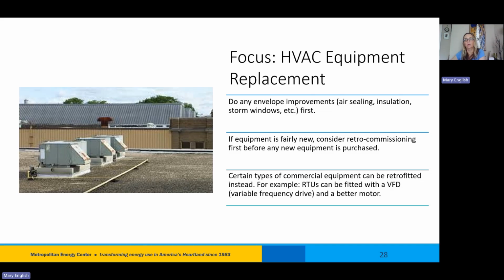Certain types of commercial equipment can be retrofitted, much like you retrofit your lighting from incandescent or fluorescent to LED, which is a huge return on investment. If you have old lighting, I'm not addressing it here since it's pretty well known—call a professional. But on the HVAC side, less well known is the fact that we have old motors. Outdated technology motors are still being installed in brand new equipment. We have much better technology that manufacturers just aren't using, due to what they want to spend money on—it's called the electronically commutated motor.